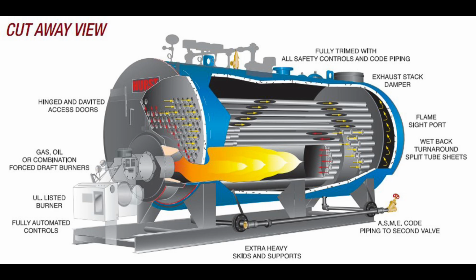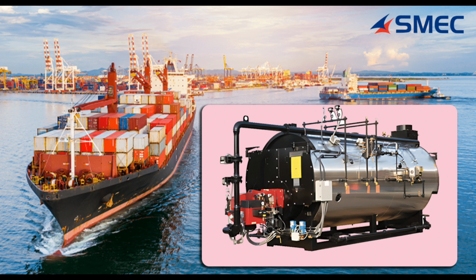So, the procedure is: drain the boiler completely, dry out the internal surface using heaters or warm air, and place desiccants like silica gel or quicklime (CaO) inside the drum to absorb moisture. Close all manholes and valves airtight and periodically check and replace desiccant if needed. Key points: ensure the boiler is completely dry, best for long-term shutdown, safe from corrosion due to lack of moisture.